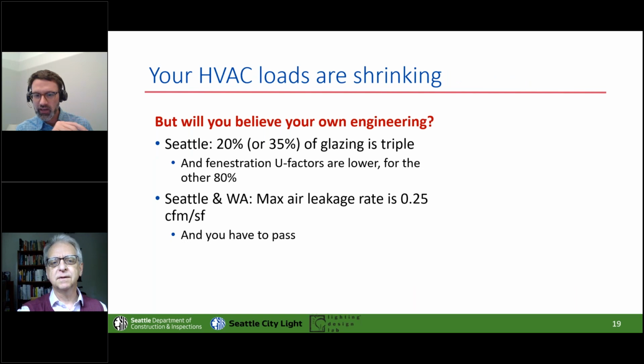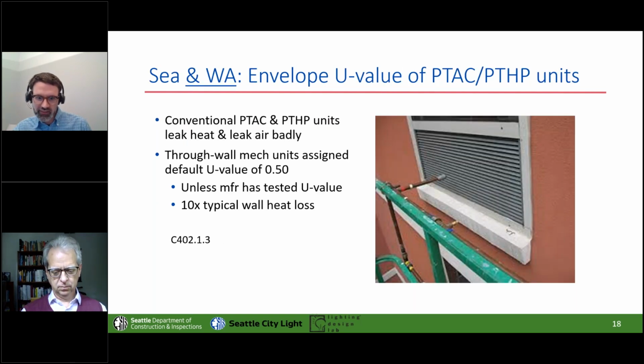Can I share a quick thing? We had an East Coast project where the contractor didn't install these well. The little flange seals that are supposed to go in got smushed and torn out of place. Because the cabinet sits negative for the VPAC versions, it just sucked air full time, so much that the building started raining—not just humidity or mold growth, it started raining inside, dripping from surfaces. We smoke-bombed one of those VPAC closets, which was really fun, and it just blew smoke out of every seam. So I back you up there.